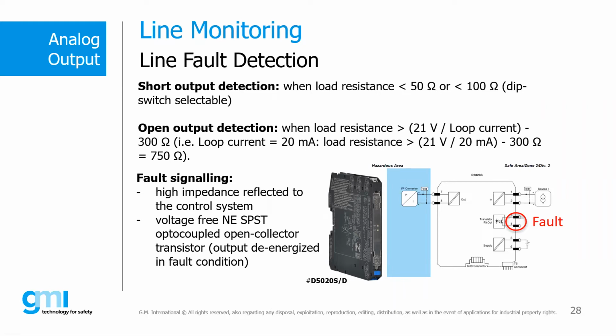In fact, when a fault is detected, the barrier's input circuit goes into a high impedance condition, typically higher than 5 kilo ohms, causing a maximum current lower than 2 milliamps to circulate in the input loop. In this way, the PLC analog output card, if supervised and able to receive this impedance variation, will understand that a fault has occurred in the field and will signal a fault. This system guarantees considerable savings in terms of cost, as it supervises the loop without the need to add a dedicated DCS system for this purpose.